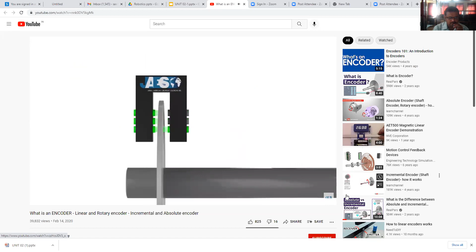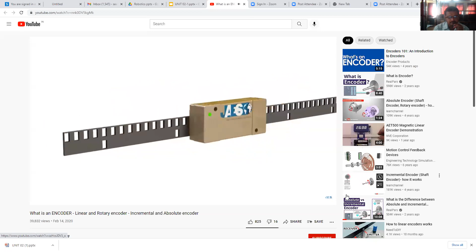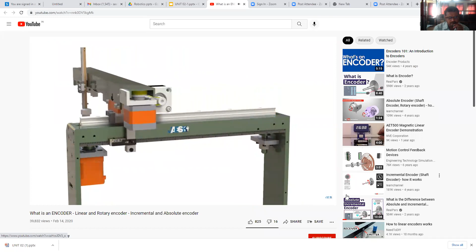In this video, we will focus on the most popular encoder technology, the optical encoder. We will see different types of optical encoders and their applications. See that they are discussing optical encoders. Let's start from the linear encoder, which is basically a transducer paired with a scale that encodes position. The transducer reads the scale in order to convert the encoded position into a digital or analog signal, which can then be decoded into position by a motion controller. It is normally used for linear measurements in order to detect the translational motion of an object. These encoders, in fact, can use a rod or a cable that is run between the encoder's transducer and the object that will be measured for movement.